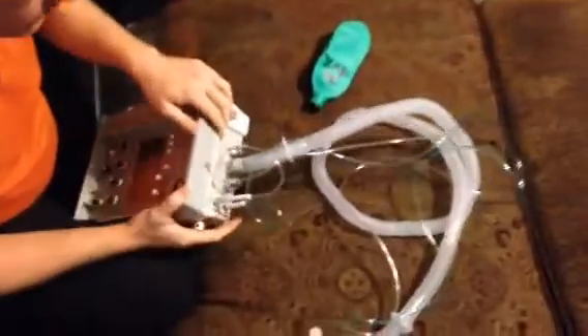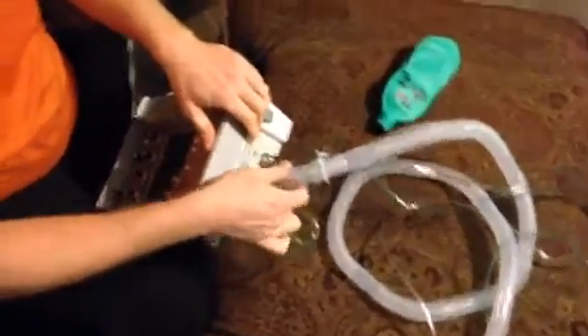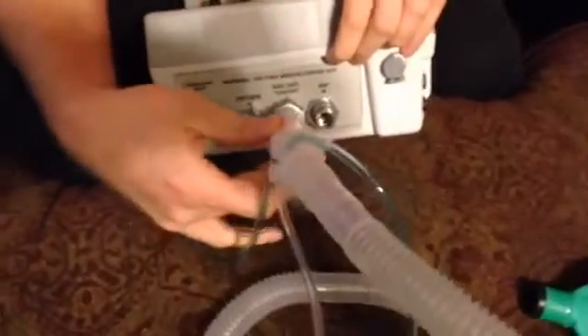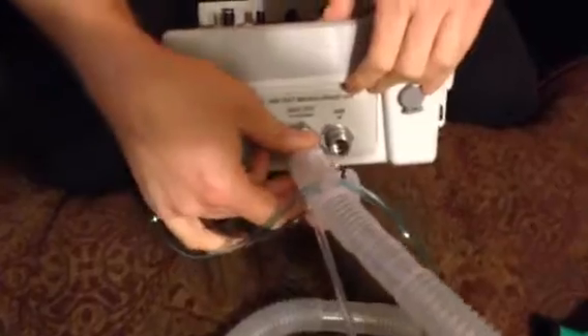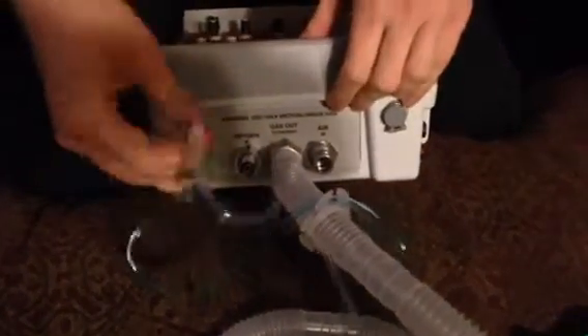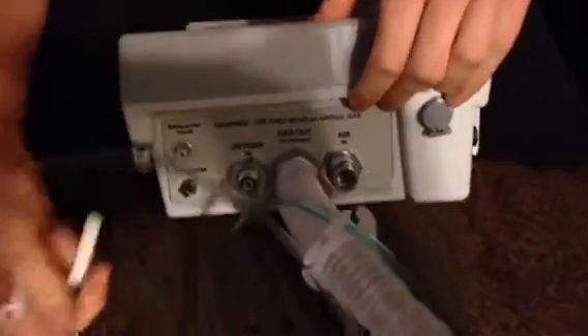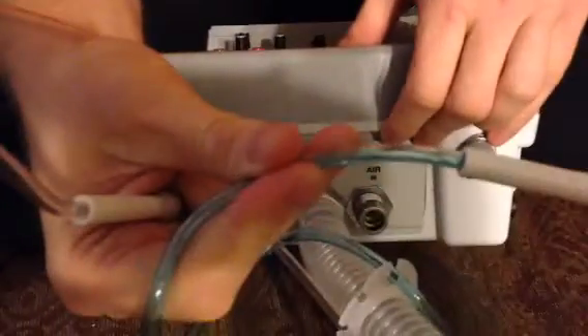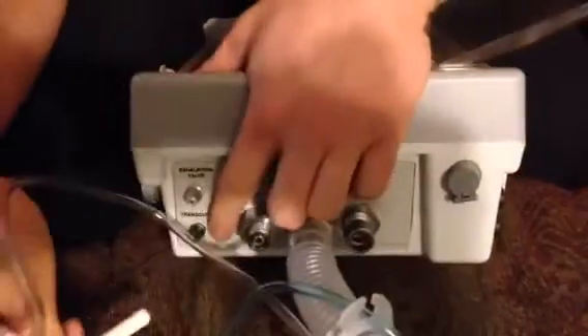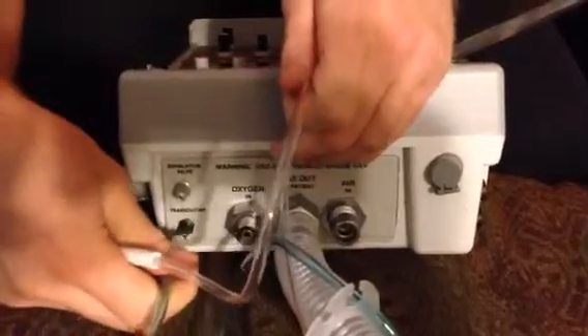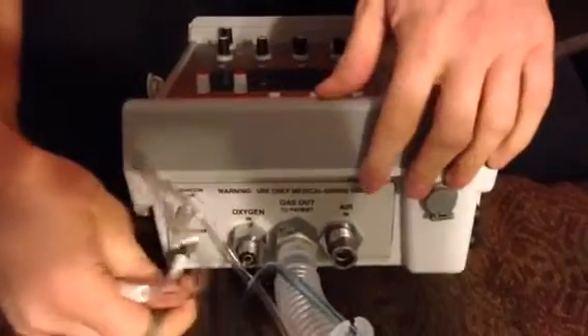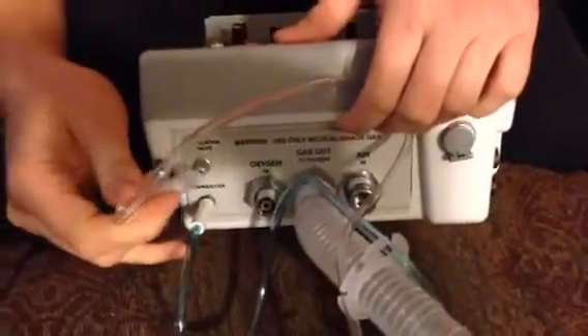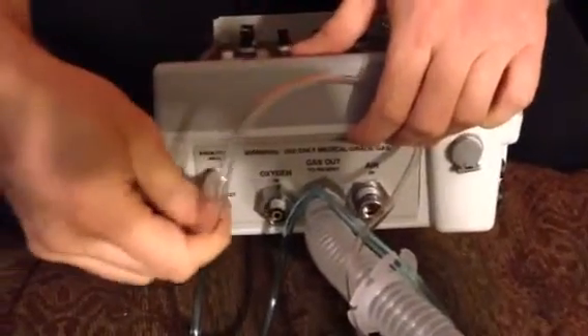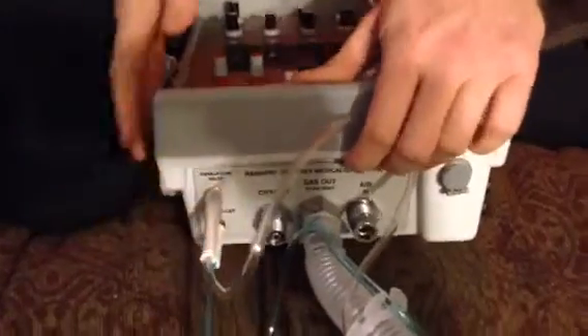Step 2. We're going to connect the ventilator circuit up to the ventilator. So we're going to connect the big corrugated tubing up to the gas out, or to patient. Next thing we're going to do is take those two little hoses. There's our pressure transducer. If you notice, it's green and the nib is green. So we're going to hook it up. And then finally we're going to hook up the exhalation valve. They only go one way, so you can't mess them up.